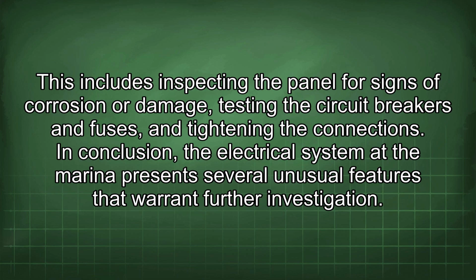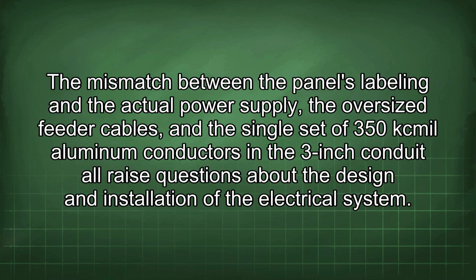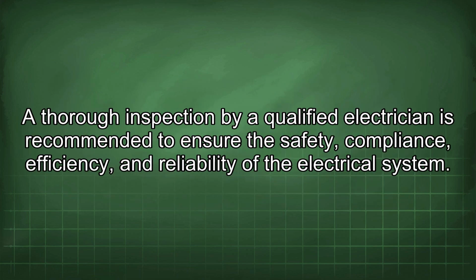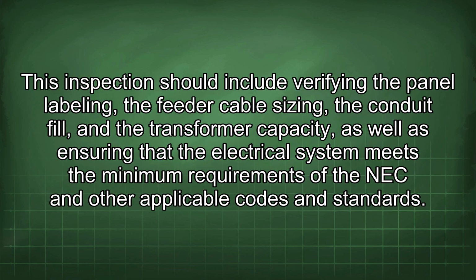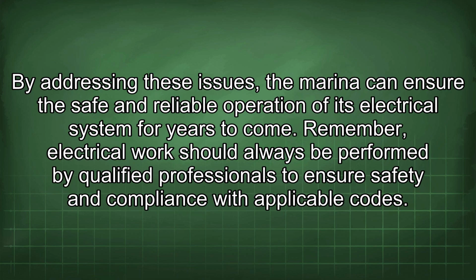In conclusion, the electrical system at the Marina presents several unusual features that warrant further investigation. The mismatch between the panel's labeling and the actual power supply, the oversized feeder cables, and the single set of 350 kcmil aluminum conductors in the 3-inch conduit all raise questions about the design and installation of the electrical system. A thorough inspection by a qualified electrician is recommended to ensure the safety, compliance, efficiency, and reliability of the electrical system. This inspection should include verifying the panel labeling, the feeder cable sizing, the conduit fill, and the transformer capacity, as well as ensuring that the electrical system meets the minimum requirements of the NEC and other applicable codes and standards. By addressing these issues, the Marina can ensure the safe and reliable operation of its electrical system for years to come. Remember, electrical work should always be performed by qualified professionals to ensure safety and compliance with applicable codes.